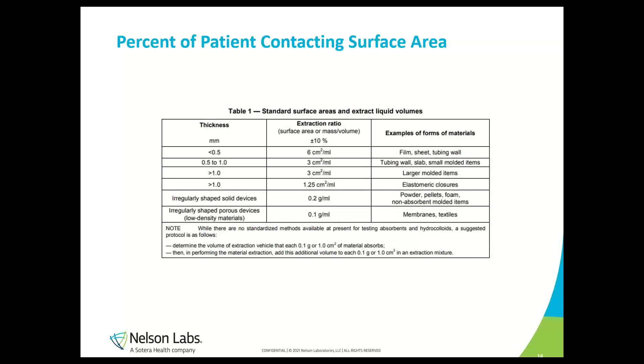And the important part here that I want to talk about with changes is this little box right here, which is the extraction ratio. It has a plus or minus 10% kind of grace period there to help labs understand that if you're within plus or minus 10%, then you can compare the results from testing. So it gives us a little bit of room with surface area calculations, and when we do our surface area.